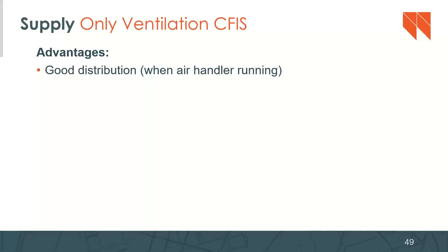You can get some pretty decent distribution. It's not great distribution. And this good distribution of the fresh air, that's to say, is only when the air handler is running. When the air handler is not running, that air is just being brought into the return duct usually. And I was just in an apartment last week where we had this kind of setup. When the air handler wasn't running, that fresh air fan was still running, and the air was just sort of falling out of the return duct, right?